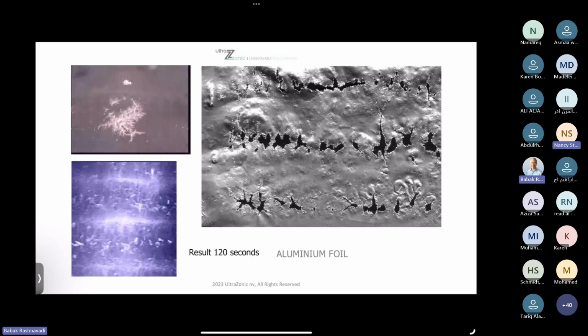You know, the most simple thing actually to check your ultrasonic device is to make a little frame, put aluminum foil on it, and then put it in your ultrasonic device. Here you can see this result after 120 seconds: you see some holes and a lot of bubbles. Now, I can tell you, if you see that kind of result with your ultrasonic cleaner in your CSSD, this is not good enough to clean your surgical instruments. Or you have to respect maybe three quarters of an hour to achieve a very good cleaning result. Okay, I will show you later with our technology what you can find out, but it's way better than what you have here. So you really have to understand, aluminum foil, when you have some holes here and there, is not good enough to clean your surgical instruments. Okay, so please next.